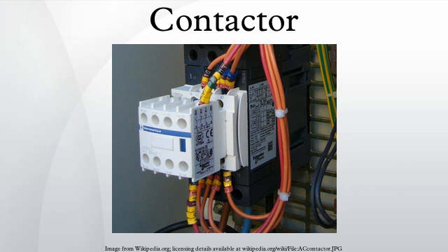Magnetic starter. A magnetic starter is a device designed to provide power to electric motors. It includes a contactor as an essential component, while also providing power cutoff, undervoltage, and overload protection. Vacuum contactor. Vacuum contactors utilize vacuum bottle encapsulated contacts to suppress the arc. This arc suppression allows the contacts to be much smaller and use less space than air brake contacts at higher currents. As the contacts are encapsulated, vacuum contactors are used fairly extensively in dirty applications, such as mining.